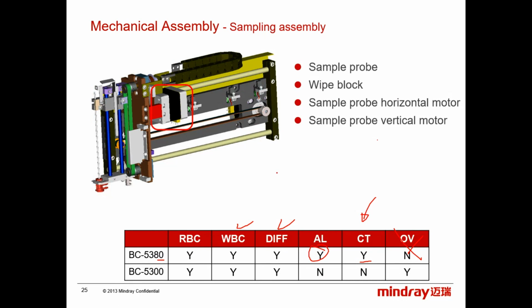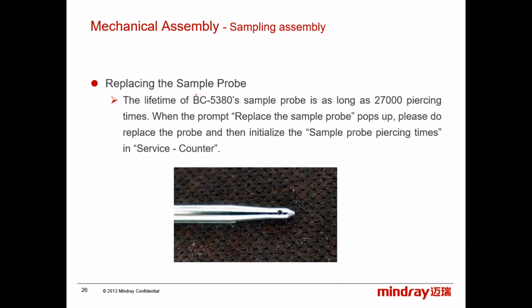So we have a probe wipe, the sample probe horizontal motor, driven by a belt, and this is the vertical. As you see here, it pierces from the side, or the hole is from the side. Normally the theoretical lifetime is 27,000 piercing times, or 27,000 cycles, okay? There is a software counter. When the analyzer reaches this number, it will give you the prompt: replace the sample probe, okay?